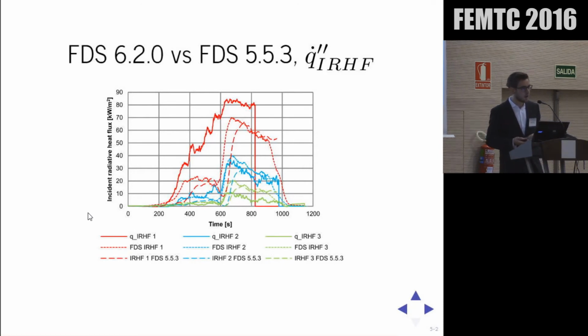A thesis from Stord Haugesund University in Norway performed numerical work on a large-scale fire test similar to this one. The main goal in that study was, however, to look at an ejecting plume and the thermal impact on steel structures outside. They discovered that FDS 553 was not able to simulate the gas temperatures out from the opening. The ejecting fire plume was ejected further away from the facade compared to the actual test data and pictures.